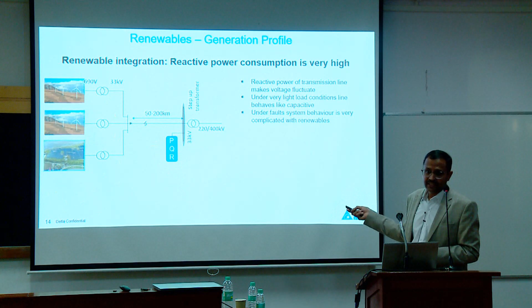Typically here we have to install power quality equipment just to make sure voltage is regulated. What is the thumb rule? If you have 100 megawatt of plant here, you should have 20% minimum. This is what China follows, but in India they are now saying it has to be 30%. The responsibility of this equipment is only to support the voltage fluctuations. Don't bother these guys to stop their generation. Let them generate. We provide the sophisticated grid. This is on the power quality side, supporting.